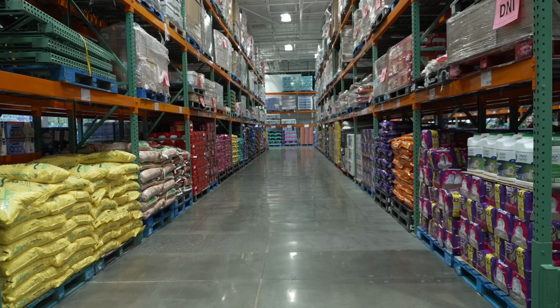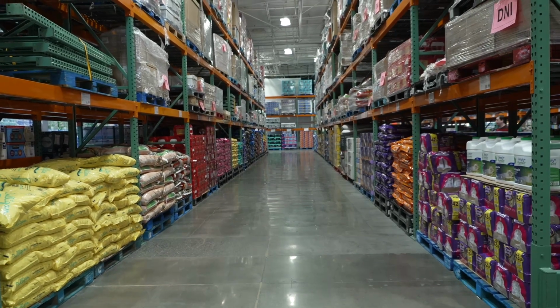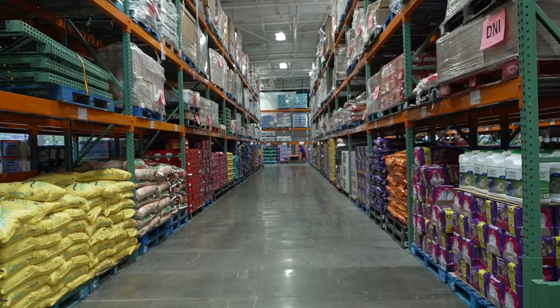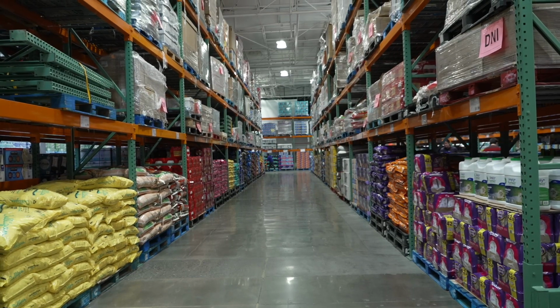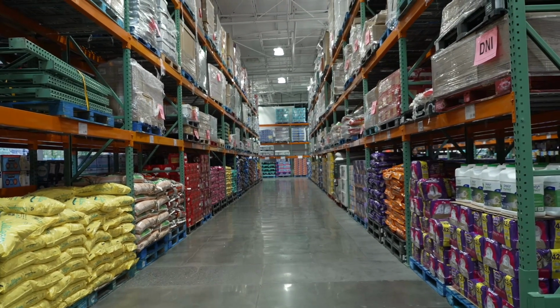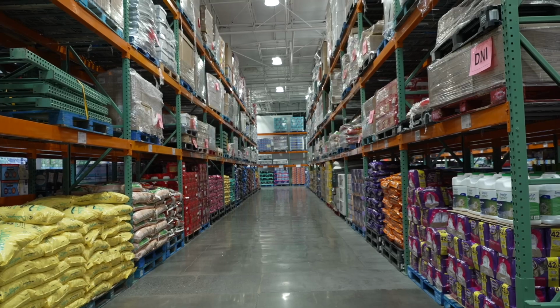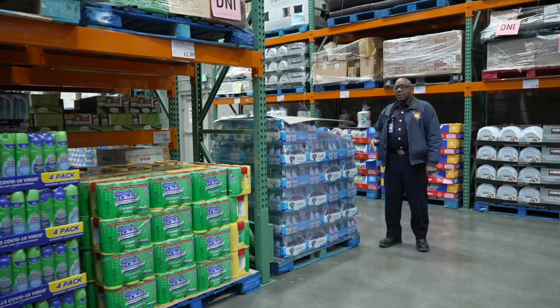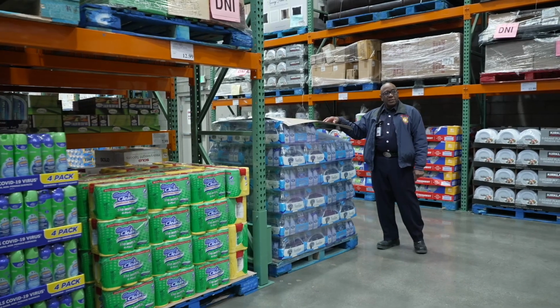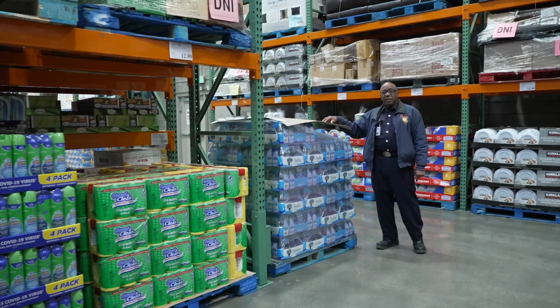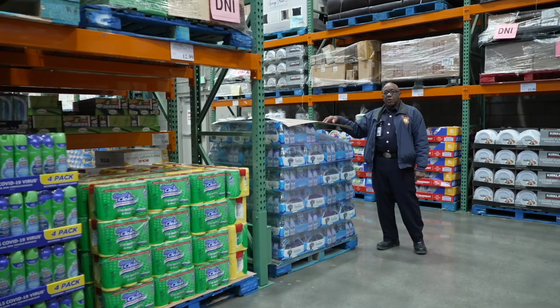Here is what a standard aisle will look like in your mercantile. This particular occupancy does a very good job of not storing outside their minimum aisle width, which is 8 feet. Here's an example of an end cap that's obstructing the aisle width that's required for high pallet storage.